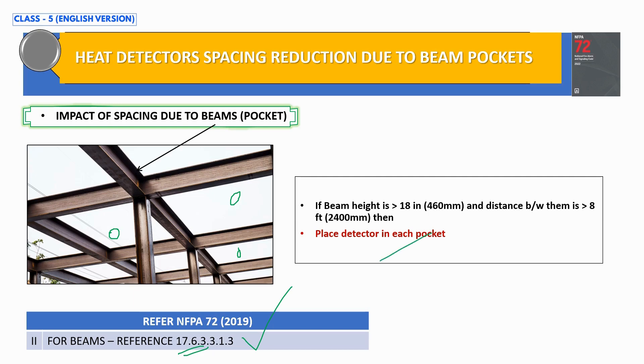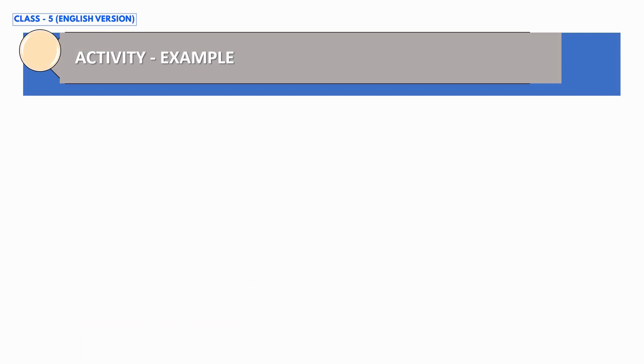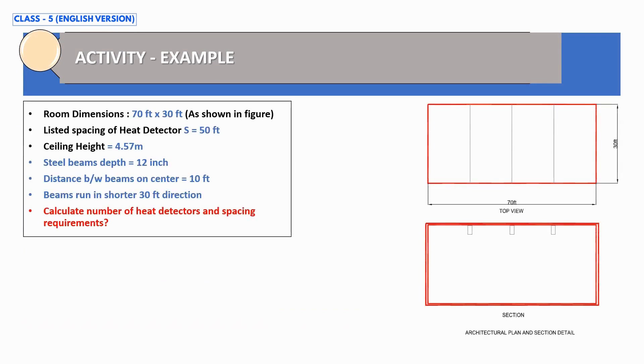In the next slide we look at an example. A particular building has dimensions of 70 feet by 30 feet, with steel beams of 12-inch depth and a distance of 10 feet between beams. The listed spacing between heat detectors is 50 feet. The ceiling height is more than 3 meters — specifically about 4.57 meters. We need to calculate the number of heat detectors and the spacing between them for this building.